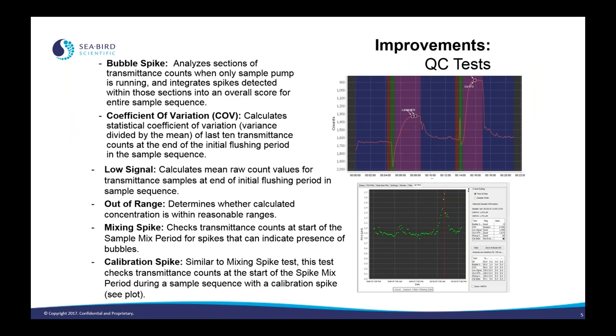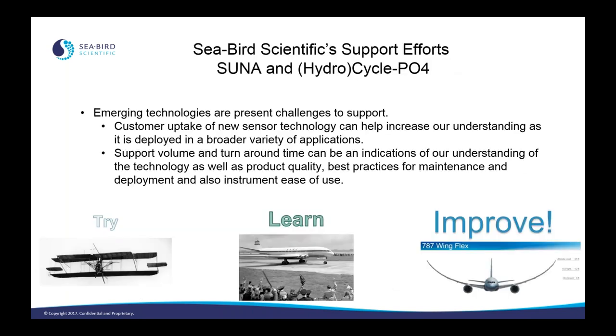The flagging system comprises a composite suite of six individual quality flags. The six flags are: bubble spike, to indicate when bubbles may influence the system; coefficient of variation, giving an idea of how well the sample worked through the fluidic chain; low signal, related to signal-to-noise ratio and out of range; and mixing and calibration spikes, indicating how the fluidic system is working. We implemented all these QAQCs and conducted training on them. This was a good challenge for any observatory to set up meaningful QAQC parameters to give data confidence through deployments.